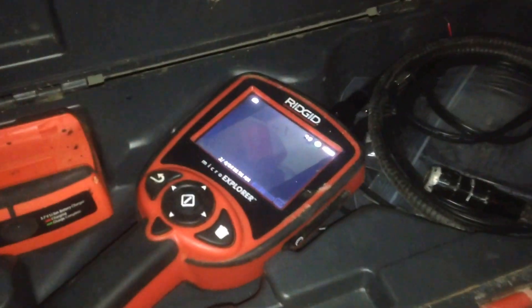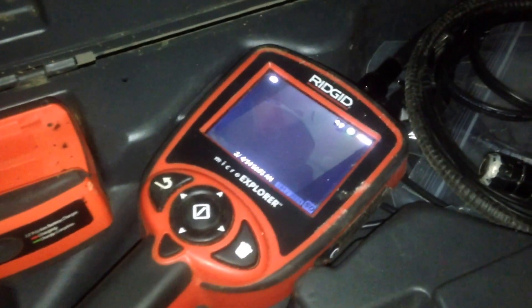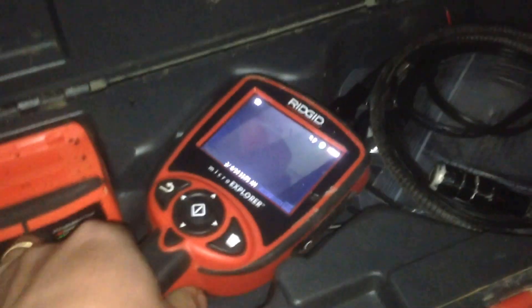We're going to do an inspection of the evaporator coil with as little intrusion as possible. I've got my RIDGID microEXPLORER camera here and we're going to run it into the return plenum to see what we've got. There's a port drilled into the plenum so I can get in there. This is the coil on this air handler, which is in stark contrast to the coil on one of the units that was replaced.